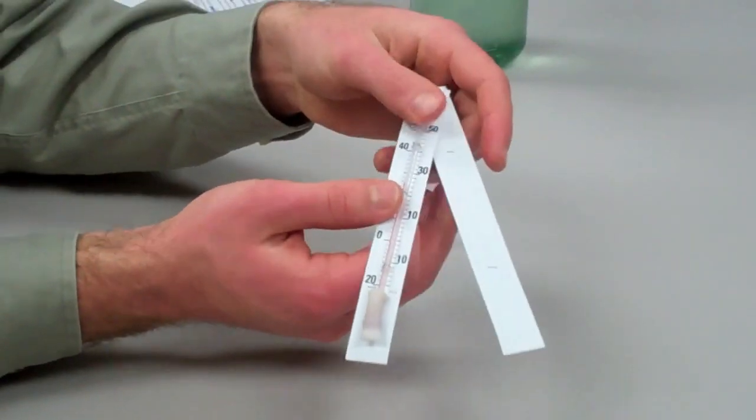Spread the thermometers apart and whirl them about for around a minute. And then look at the wet bulb to see the difference between it and the dry bulb temperature. This is the wet bulb depression.